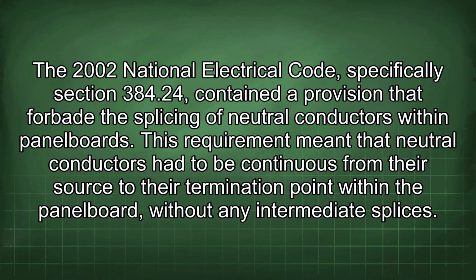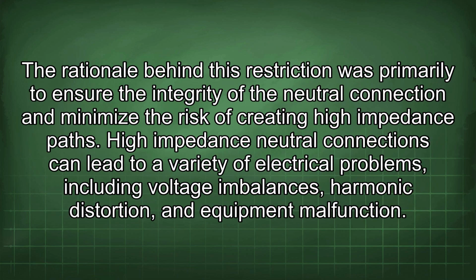The 2002 National Electrical Code, specifically Section 384.24, contained a provision that forbade the splicing of neutral conductors within panelboards. This requirement meant that neutral conductors had to be continuous from their source to their termination point within the panelboard without any intermediate splices. The rationale behind this restriction was primarily to ensure the integrity of the neutral connection and minimize the risk of creating high impedance paths.